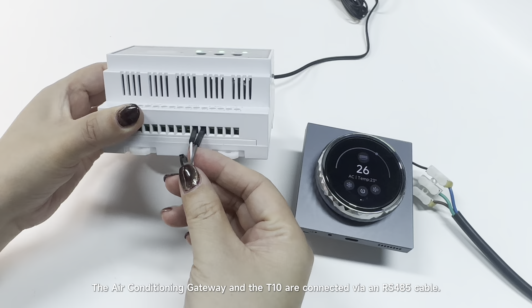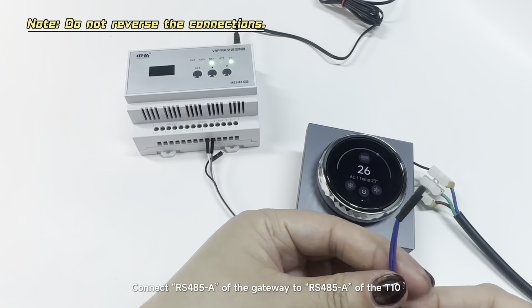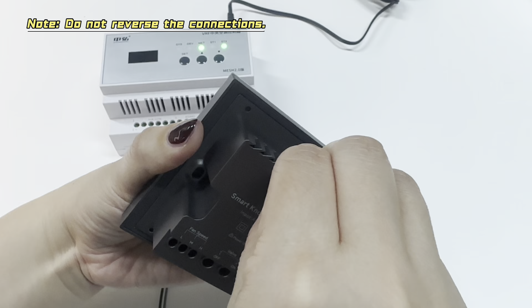The air conditioning gateway and the T10 are connected via an RS485 cable. Connect RS485A of the gateway to RS485A of the T10 and RS485B of the gateway to RS485B of the T10. After the wiring is completed, enter the device settings interface.